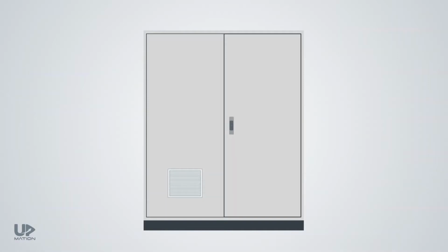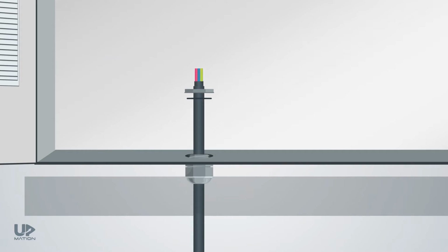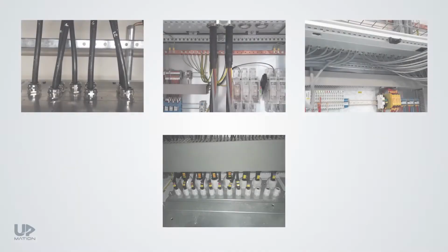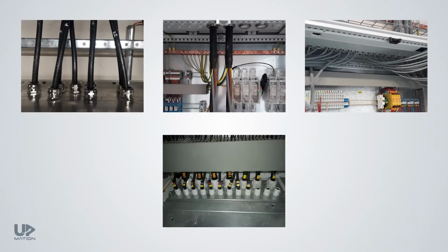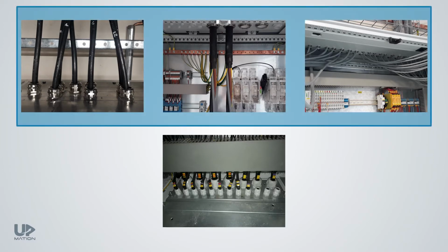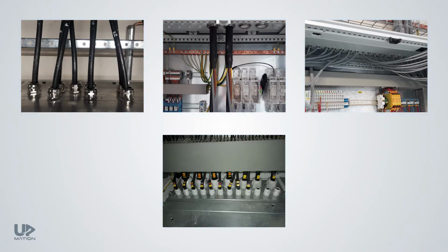There would be the same procedure as the motor terminal box for the electrical panels. This time, after I install the gland on the cable, I will pass it through its specific hole on the gland plate. I adjust the length of the cable that I need within the electrical panel and then fix the gland on the gland plate. Here you can see some cases of installed glands on the gland plates on top or on the bottom of the panels. As you see, the cable glands are applicable for all kinds of the cables like power or instrumentation.